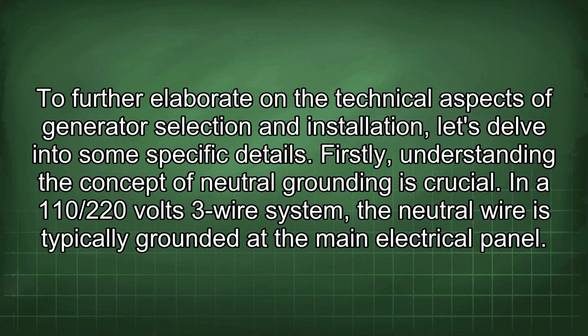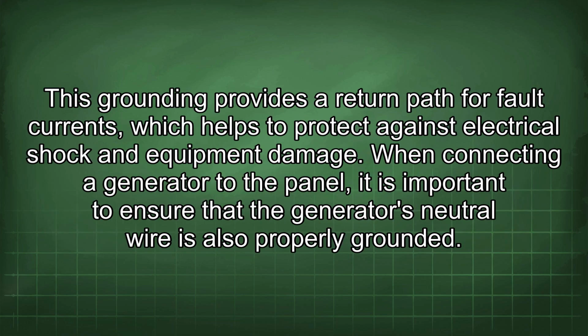Firstly, understanding the concept of neutral grounding is crucial. In a 110/220 volts 3-wire system, the neutral wire is typically grounded at the main electrical panel. This grounding provides a return path for fault currents, which helps to protect against electrical shock and equipment damage.